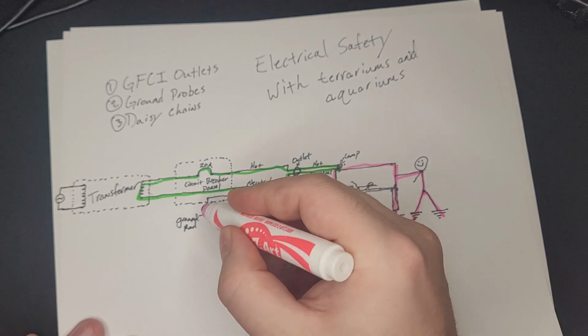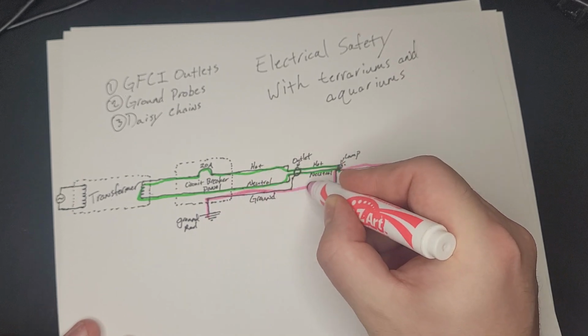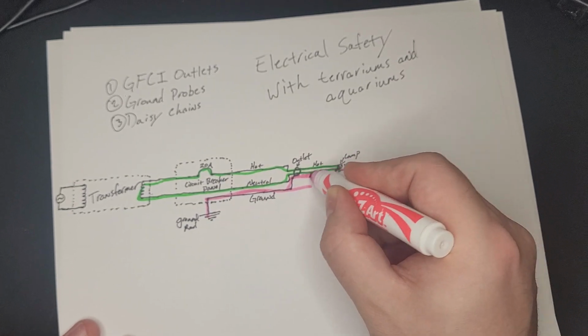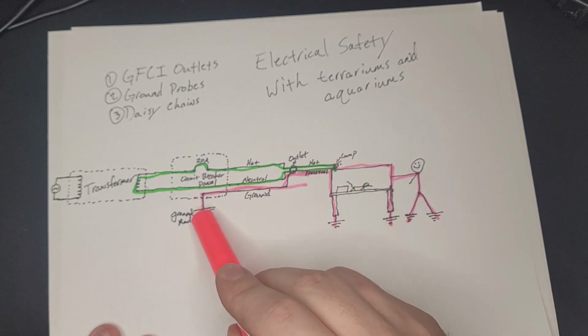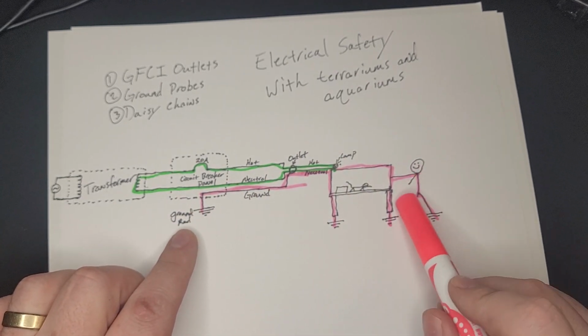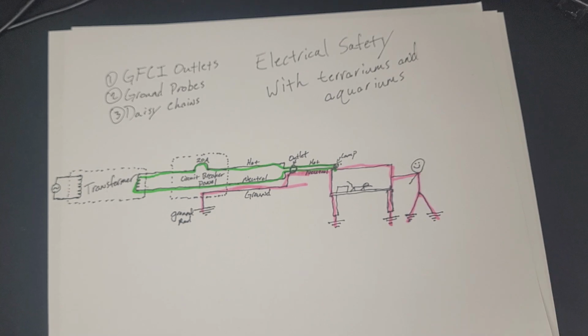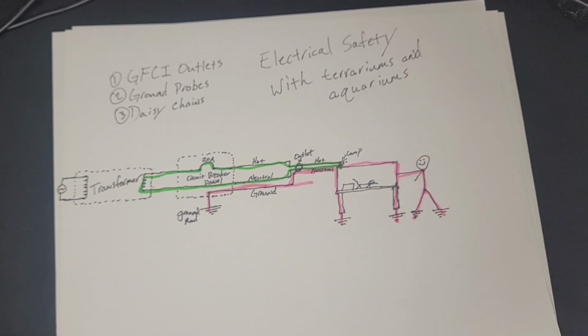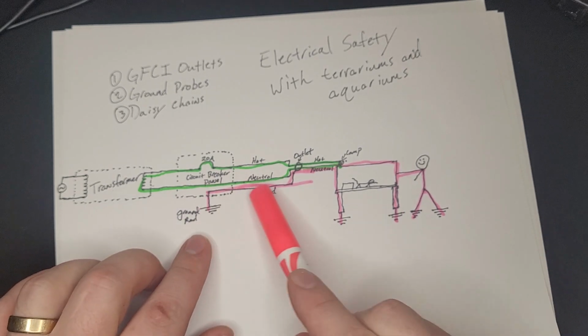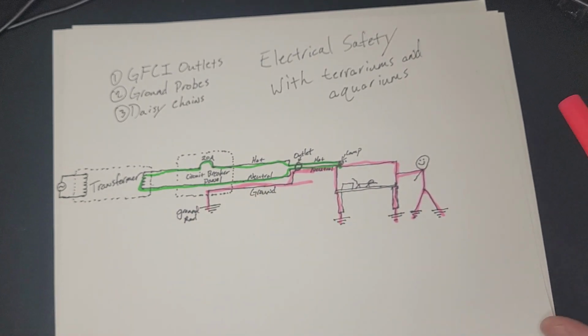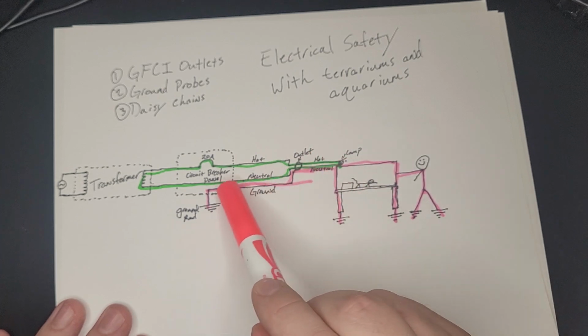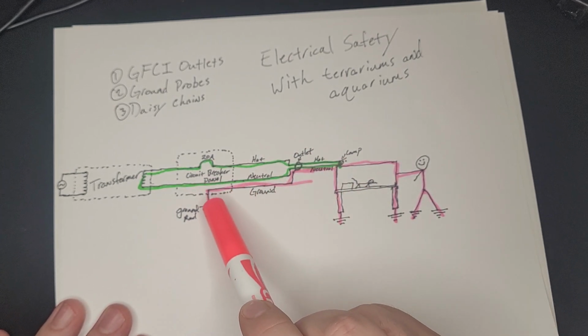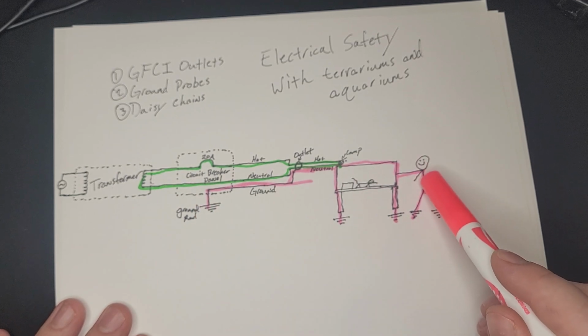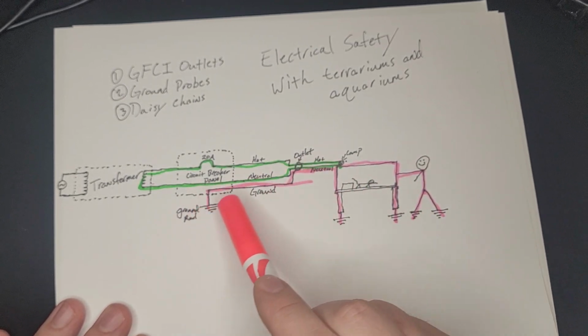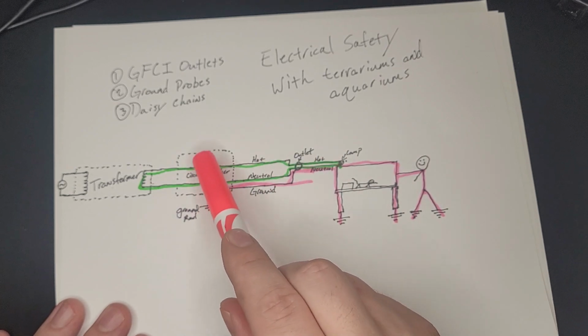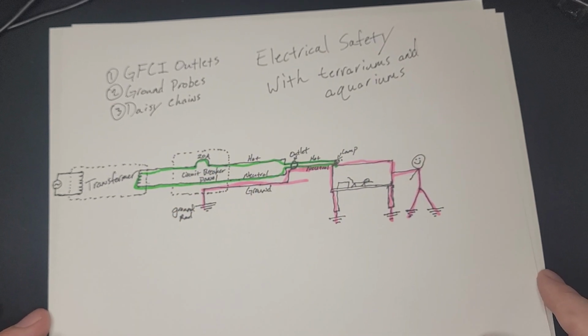That's the purpose of the ground wire, to provide a short circuit path to ground that's very low resistance, diverting a lot of electricity so it doesn't go through your body. A human body's resistance varies, but on the low end it's a few thousand ohms, whereas a ground wire is pure copper, only a few milliohms. So the current takes the path of least resistance, and most of it flows through the ground wire, making it less likely to hurt you. You still get a rush of current, and it still trips the 20 amp breaker, so that part is the same.